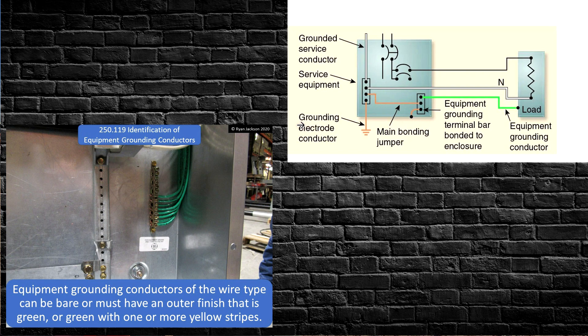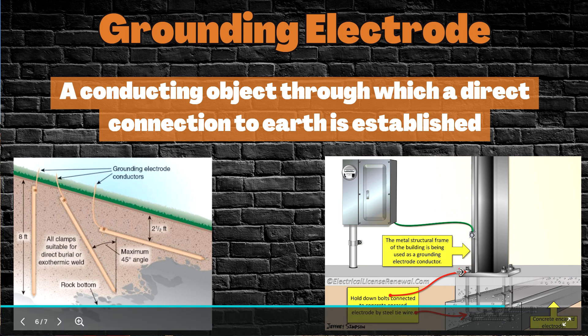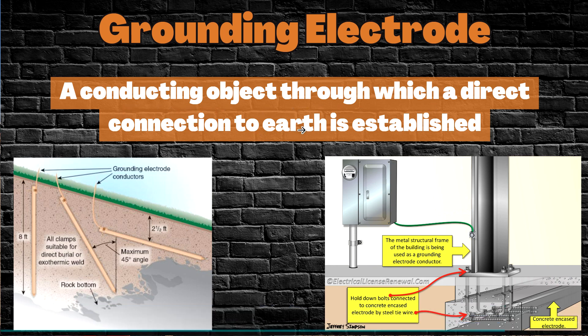Next is the grounding electrode. A grounding electrode is a conducting object through which a direct connection to earth is established. The grounding conductor is connected to the grounding electrode. One example shown is a concrete-encased electrode, where the metal frame is attached to bolts connected to rods running through the concrete — that's your grounding electrode. Another easy example is ground rods, which are also grounding electrodes. Simply put, it's a conducting object through which a direct connection to earth is established.